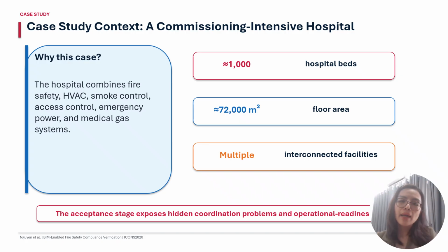The case study context: a commissioning-intensive hospital with a floor area of more than 72,000 square meters, nearly 1,000 hospital beds, and multiple interconnected facilities. Why do we use this case? Because the hospital combines fire safety, HVAC, smoke control, access control, emergency power, and medical gas systems. So the acceptance test exposes hidden coordination problems and operational readiness.